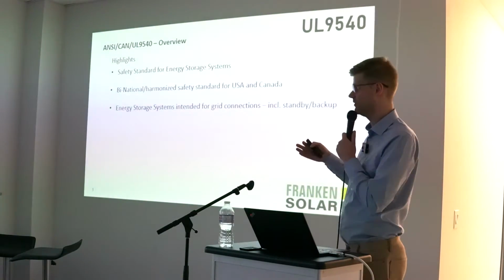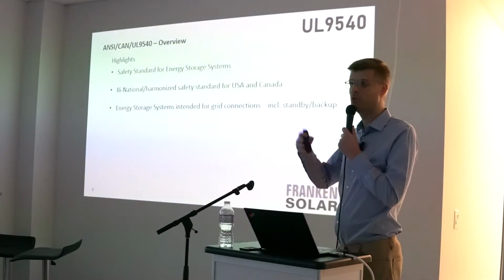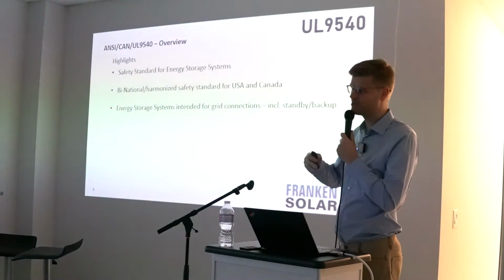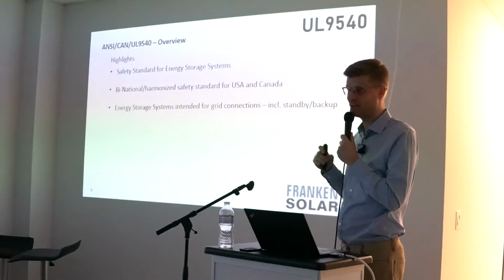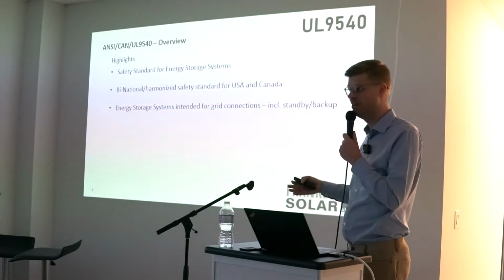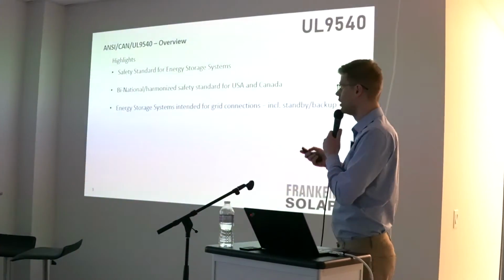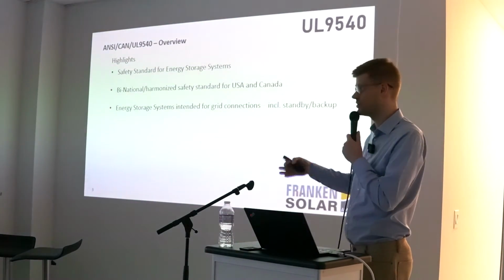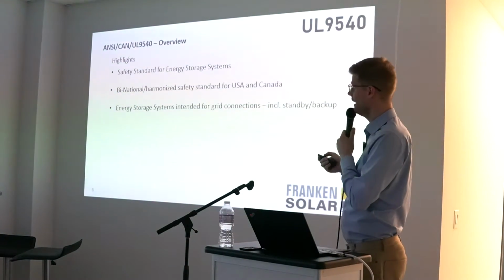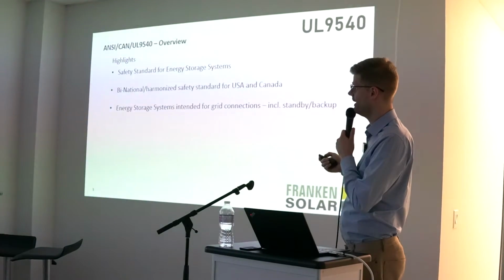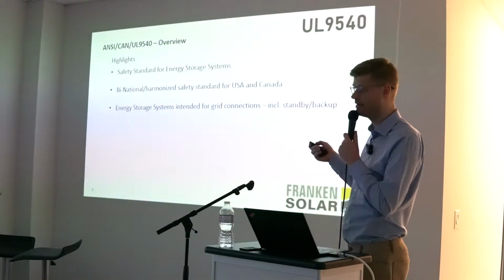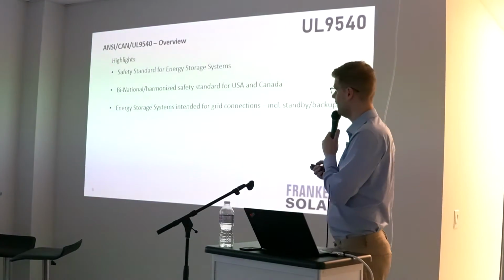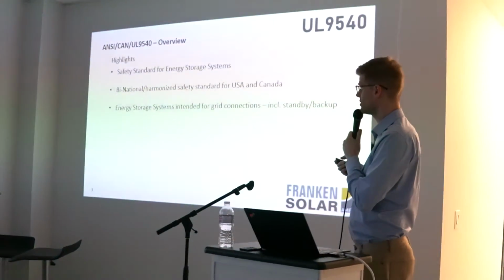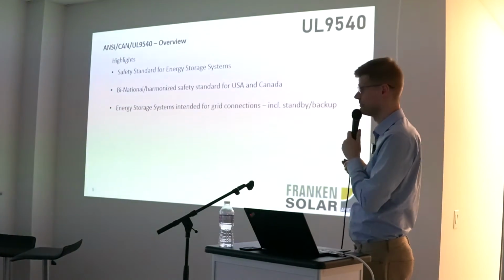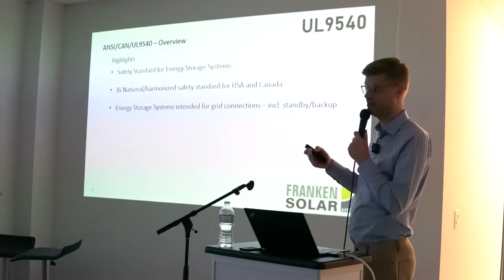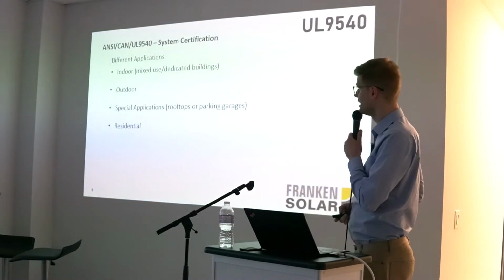In the past, a lot of the certifications we see is a UL certification. And then the Canadian certification is similar, but not the same, has a different name, and there's a lot of confusion about what is now actually required. Going forward, it's one testing, one certification that applies to both countries. And that's why it's also called ANSI CAN UL for the Canadian and the US market. And then that code mainly applies for energy storage systems intended for grid connections. And that includes standby and battery backup systems.